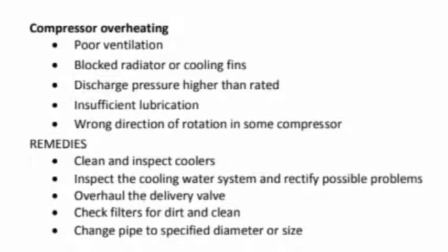Possible remedies: number 1, clean and inspect coolers. Number 2, inspect the cooling water system and rectify possible problems. Number 3, overhaul the delivery valve. Number 4, check filters for dirt and clean them. Number 5, change pipe to specified diameter or size.